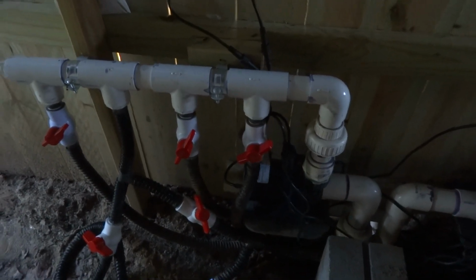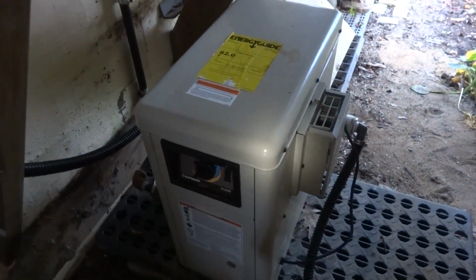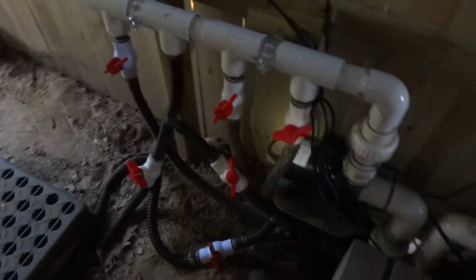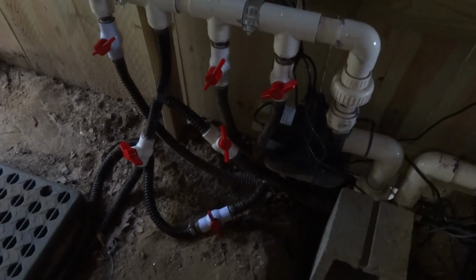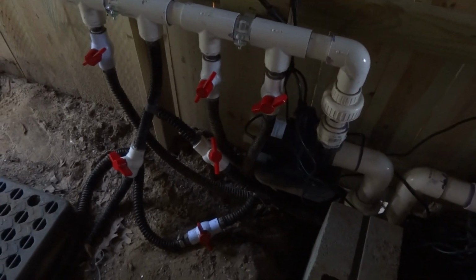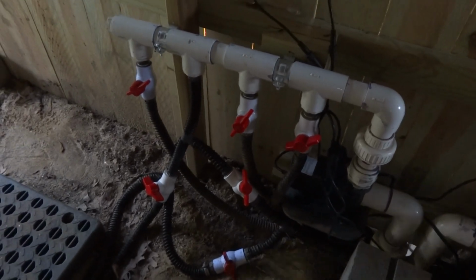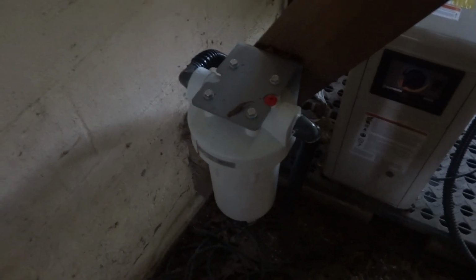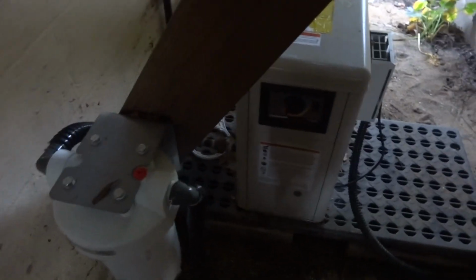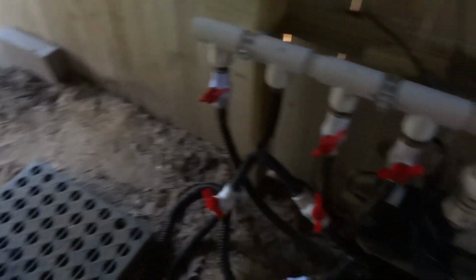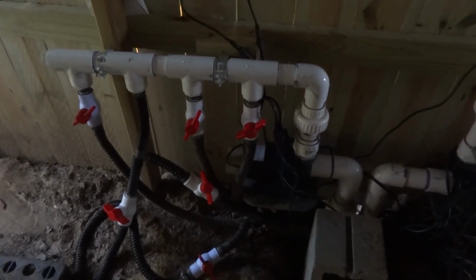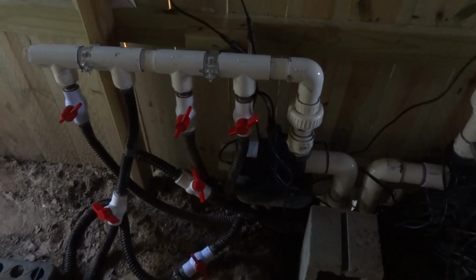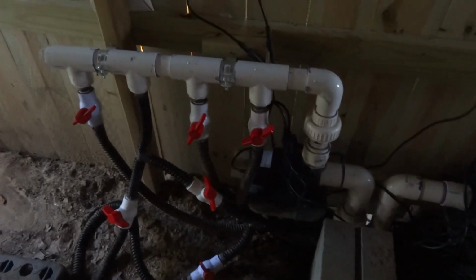This here also goes to our heater. This is a 100,000 BTU heater, and what I did is I have it where I can shut the main flow from going back into the waterfall. Instead, it goes through the heater, and you have to have a simple filter to filter out stuff, plus there's a lot of chemistry. You want to make sure your pH and your chemicals are right, because you don't want to rot out your coils and stuff inside your heater. So this is how we got this.